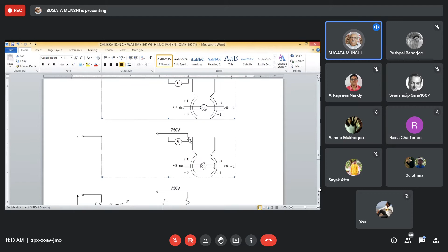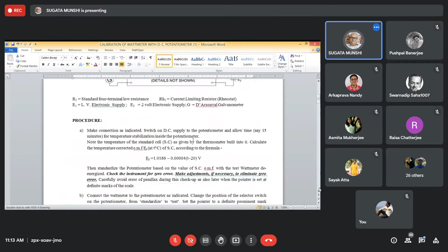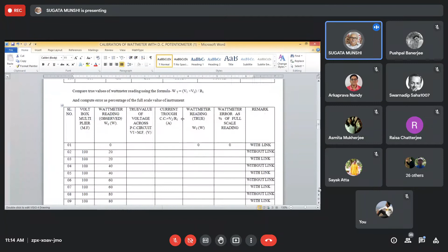If the temperature to which the cell is exposed is something other than 20 degrees centigrade, there is a definite correction formula, given in your instruction sheet. You read the temperature from a thermometer, the room temperature, and using this formula, ET equal to 1.0186 minus 0.0000404 into (T minus 20) volts. So for the standard cell, not only is the voltage accurately known, but its pattern of variation with temperature is also accurately known.